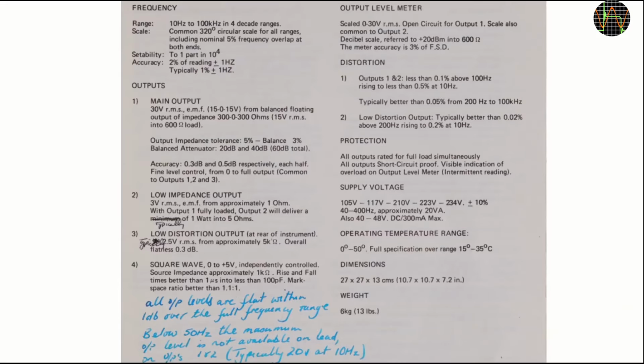To start with, my unit is the J3, not the slightly improved J3B, for which many more sources for the manuals are out there. There are differences in the schematic, so getting the right manual matters. The only J3 manual I found has some handwritten annotations from a user based, of course, on his or her J3, which may or may not apply to other J3s. Anyway, the frequency range goes from 10 Hz to 100 kHz. Above 100 Hz, the front outputs have a distortion of less than 0.1%, typically better than 0.05% from 200 Hz onwards. The rear output is better than 0.02%.